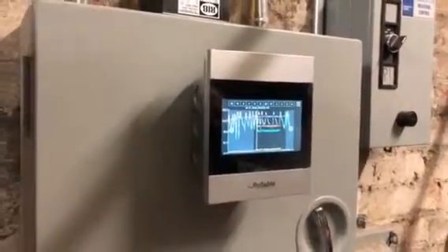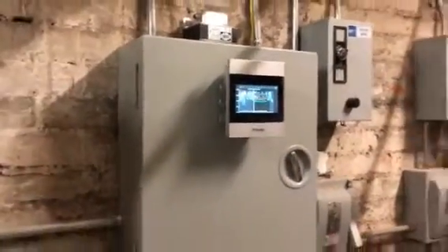And like I said, we have alarms on everything, so if we're calling for a pump to run and we have no status, that's going to be an alarm. And these pumps will automatically lead lag, and if one fails, we automatically switch over to the other one. So we're doing everything we can to keep the building warm when we're calling for it. Now, on the lead lag, does that switch weekly? Yep, Monday morning at 5 is our standard, that's typically when we switch equipment over. So that's automatic, and like I said, if there's a failure, we'll bring on the other pump to make sure we keep heating.